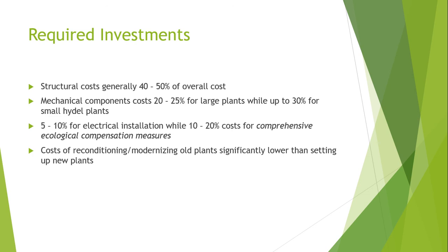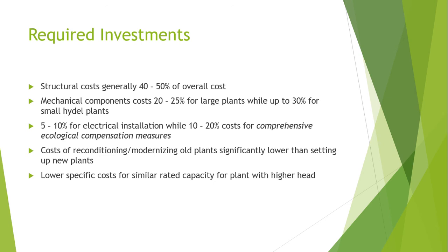Independently, costs for today's increasingly comprehensive ecological compensation measures can account for about 10 to 20 percent of the overall plant cost. This is especially true for runoff power stations with large catchments, where expenditures for the appropriate design and structuring of reservoirs — for example, fish ladders — can lead to significantly increased overall cost.